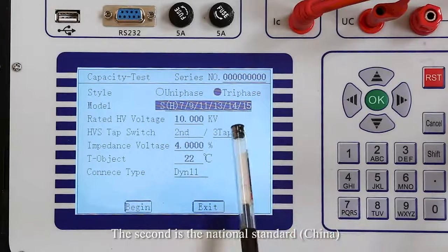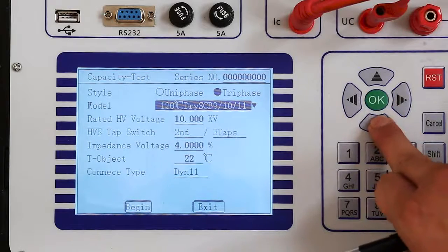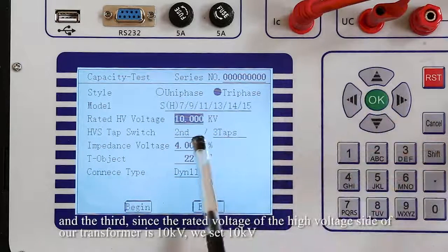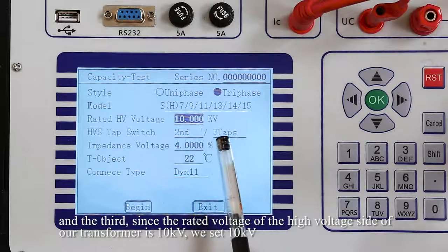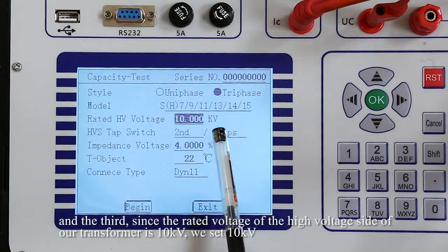The second is national standard. And the third, since the rated voltage of the high-voltage side of our transformer is 10kV, we set 10kV.